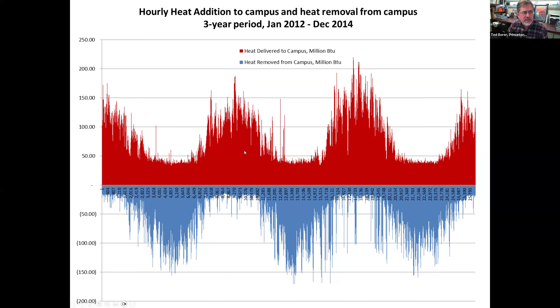So basically in the summer, I need to remove a lot of heat, and I don't have a lot of heat I need to deliver, just domestic hot water and the losses from our steam system. So if I eliminate the losses from my steam system, the blue curve, heat removal, and the red curve, heat delivery, almost exactly overlap each other. So we're right in the sweet spot where our energy recovery from the summer should be really close to our energy need during the winter.